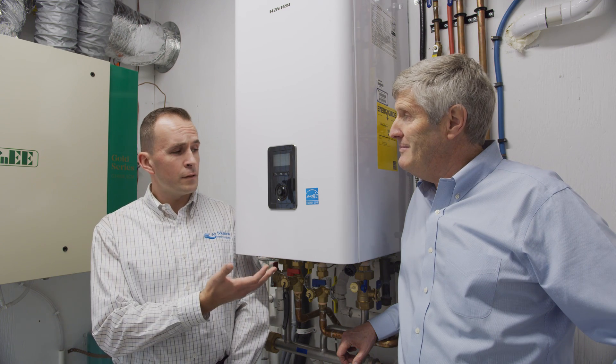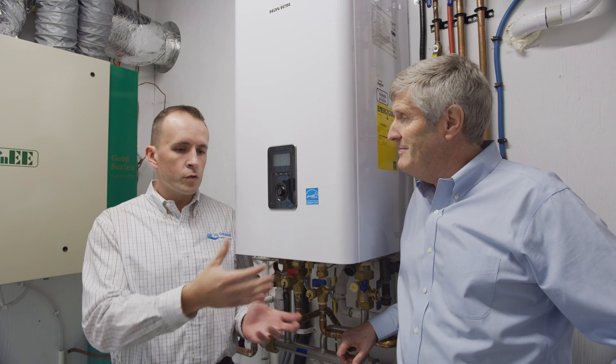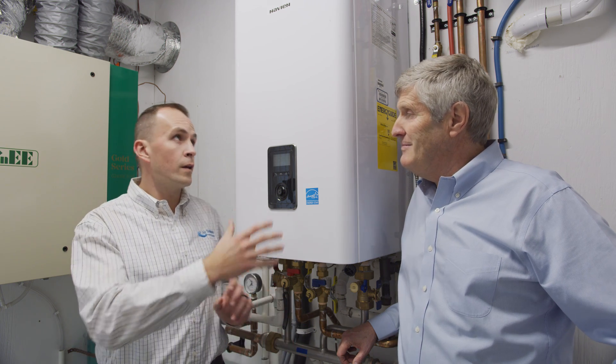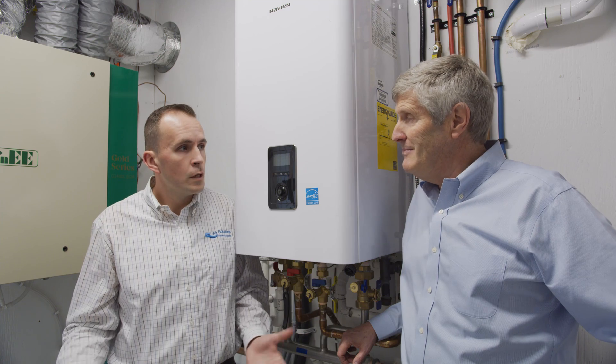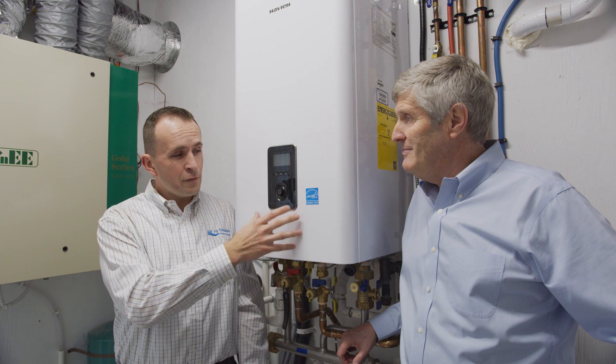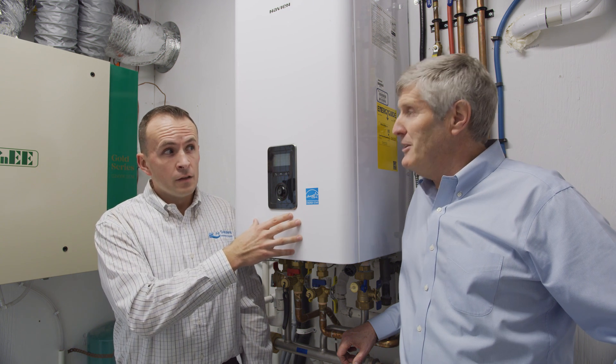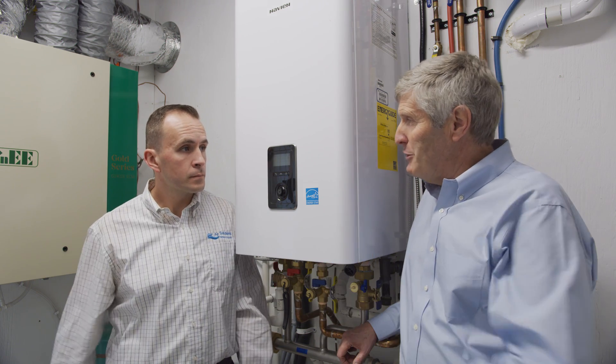From a domestic flow perspective, when we crunch the numbers, an older design parameter would tend to be a heating boiler with an indirect storage tank. That can be large and take up a lot of space, and nowadays people want more usable square footage. When we look at the flow rate of this unit, it's effectively like the steady state delivery of an 80-gallon indirect — so quite significant — and that's in a really compact size.